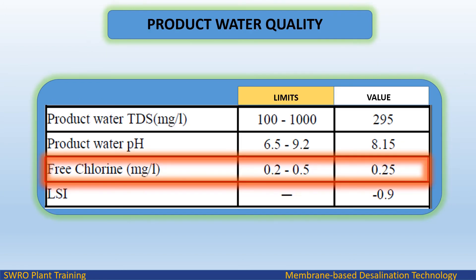After the post-treatment process, the free chlorine is maintained in the range of 0.2 mg/L to 0.5 mg/L. A minimum residual chlorine concentration of 0.2 mg/L must be maintained in the drinking water supply system through to the very end of the distribution network. Increasing the dose at the RO plant may help to ensure an adequate chlorine residual concentration throughout the distribution network.